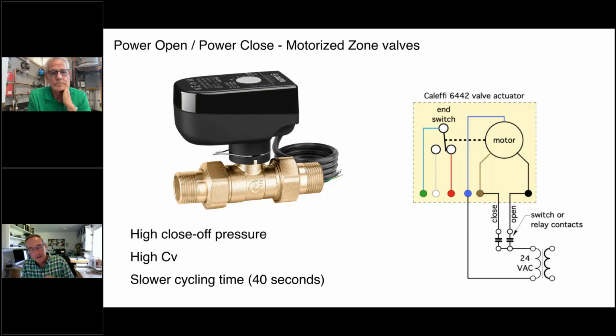And once the shaft, the ball, is fully open, the unique thing about this valve is it does not continue to draw power. So it draws about 4 watts of power when it's actually motoring the shaft open, but when it gets to the end, that power requirement goes to 0. So that valve can sit there for hours in the open position, not drawing power. And in some applications, maybe off-grid applications, that's a nice feature. It also has a single pole double throw switch in it. So you have a normally closed as well as a normally open contact. You can use those to signal other control components in the system.